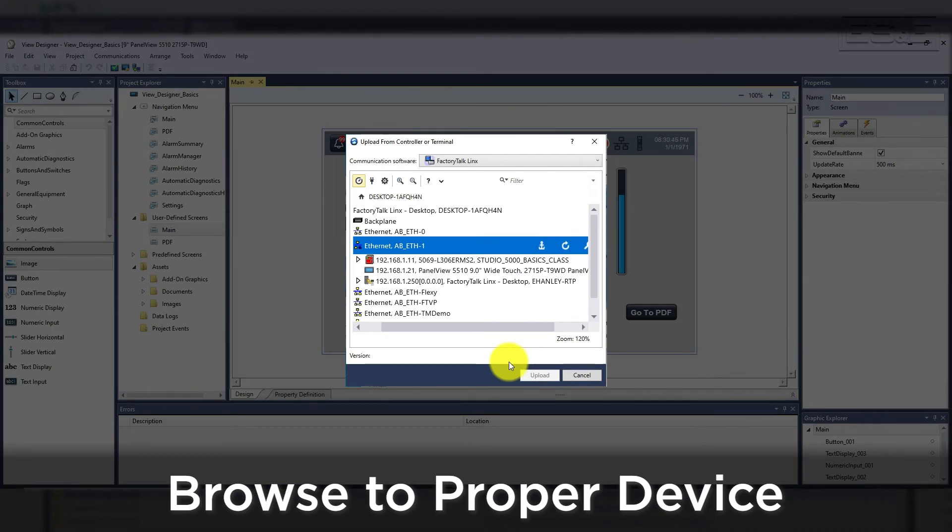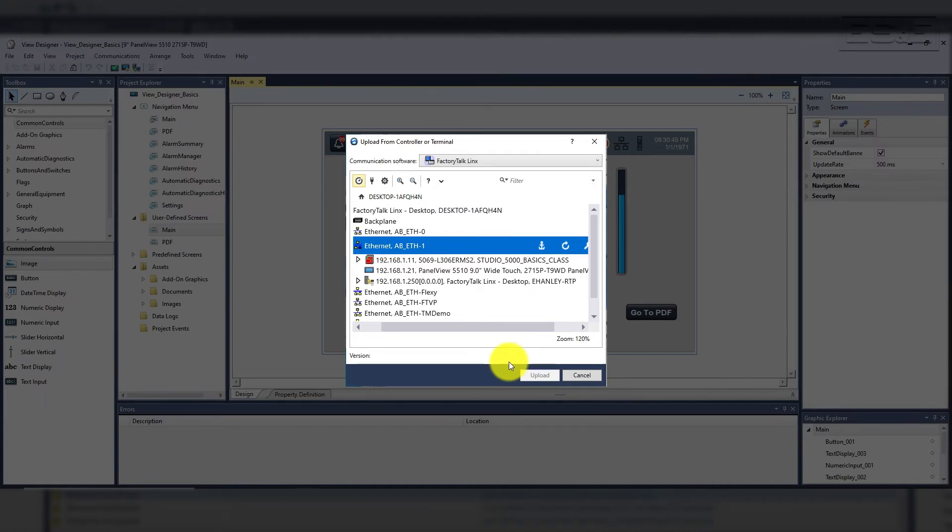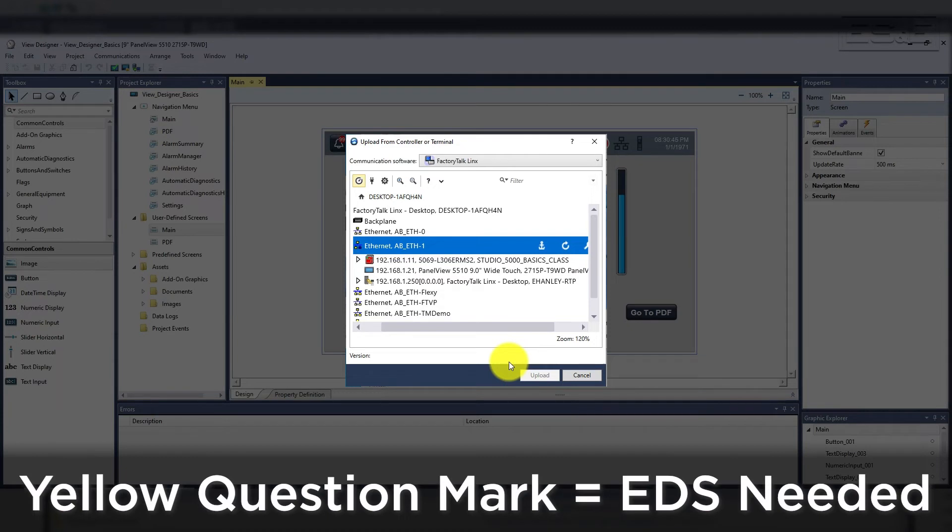Once you find the device, as long as you have the same major revision, it will upload and create a new project on your computer. If the device shows up as a large yellow question mark, then you need to upload the EDS file from the device first.